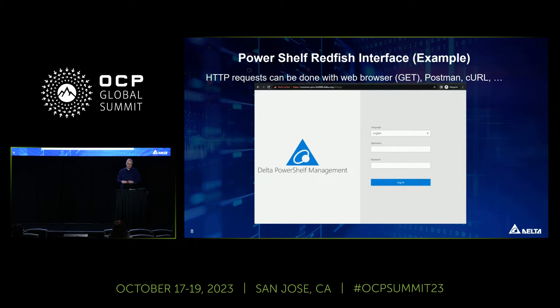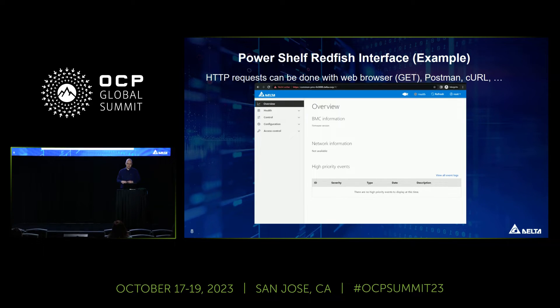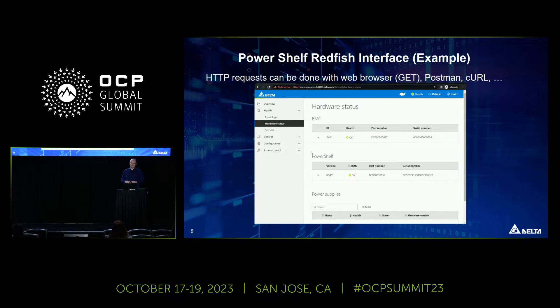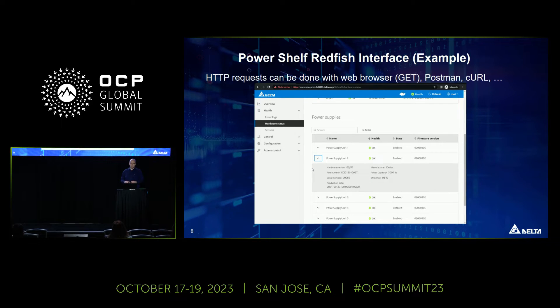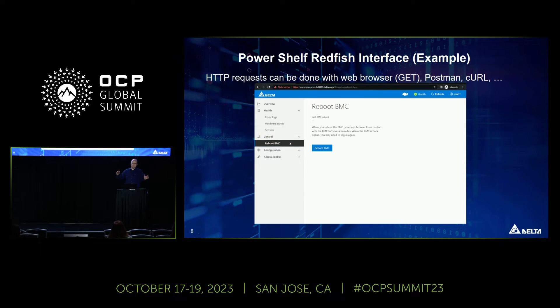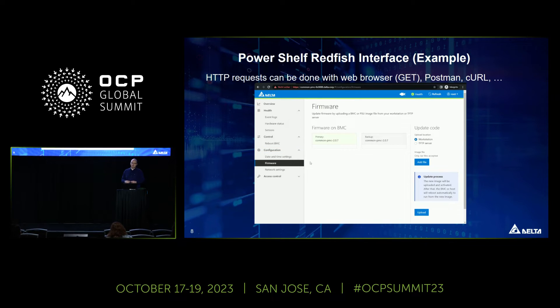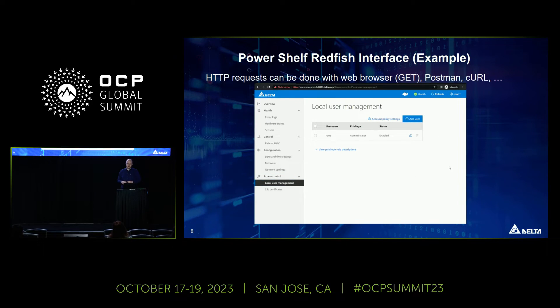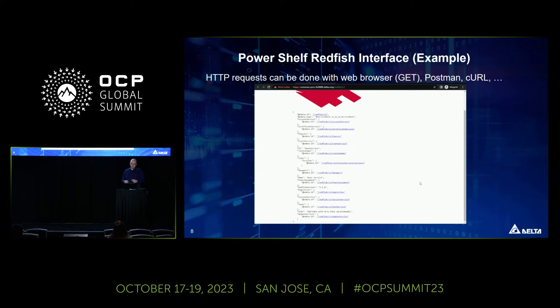We also have a web interface based on the OpenBMC webui-vue project, customized for our PowerShelf. Here you can see general information like event logs, hardware information about the PowerShelf and power supplies, and you can read and filter all sensor data. The web UI covers a subset of Redfish features but handles the most basic needs. It's a nice entry point before diving into Redfish directly, and you can also browse the Redfish interface itself directly in your web browser.